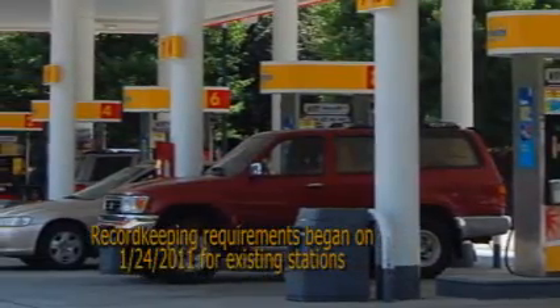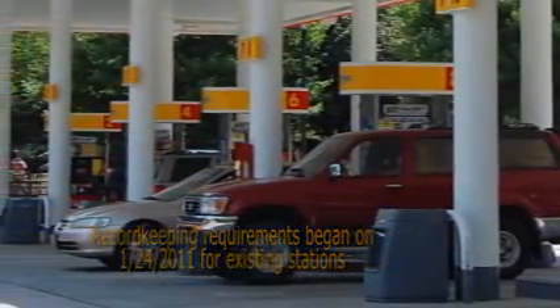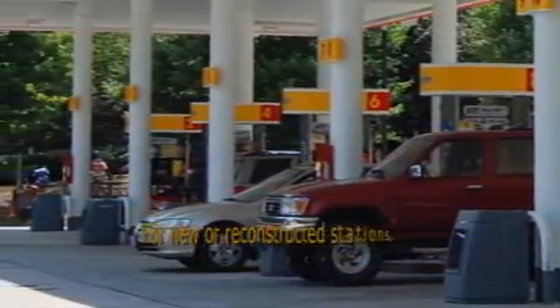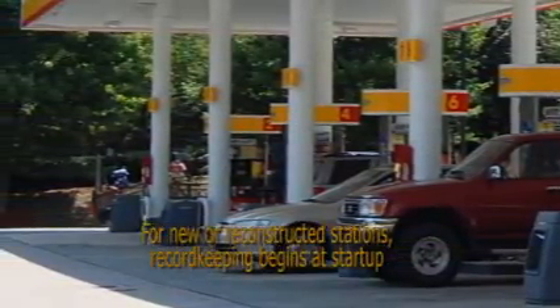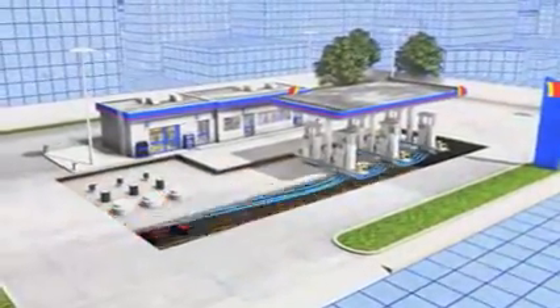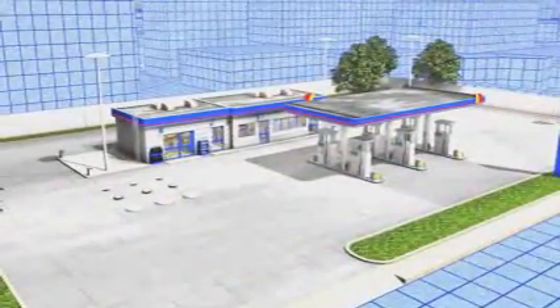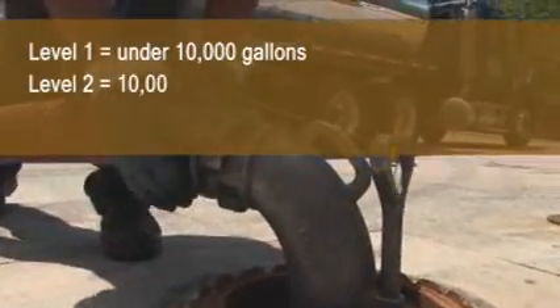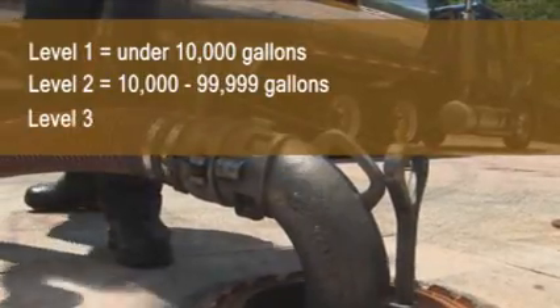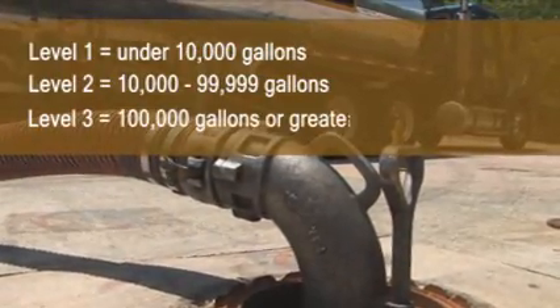Note that record keeping requirements began on January 24, 2011 for existing stations. For new or reconstructed stations, record keeping begins at startup. A new station is a source that began construction after November 9, 2006. There are 3 increasing levels of control depending on your monthly gasoline throughput. In other words, the greater your throughput, the more requirements you must meet.